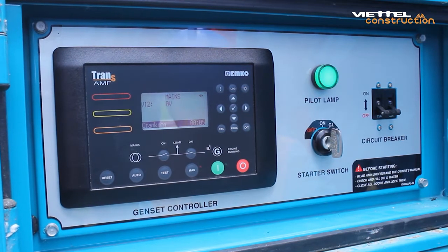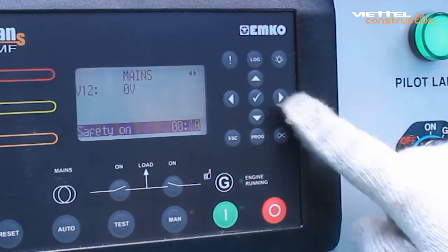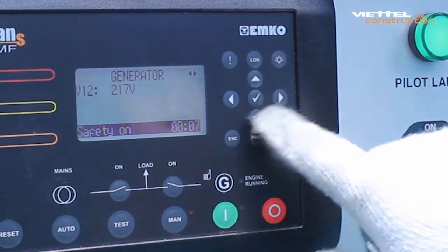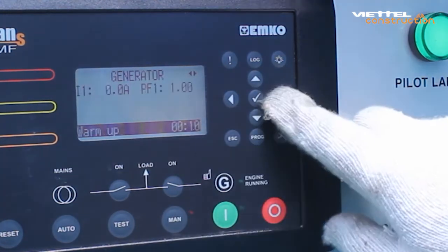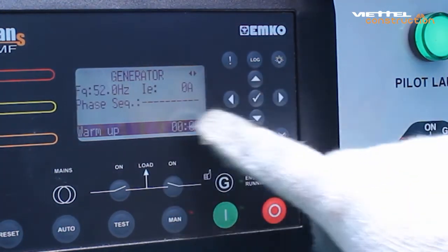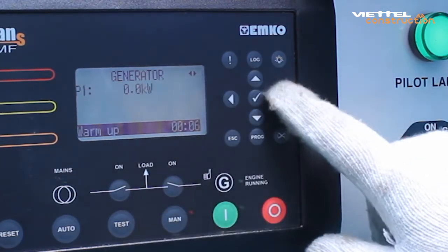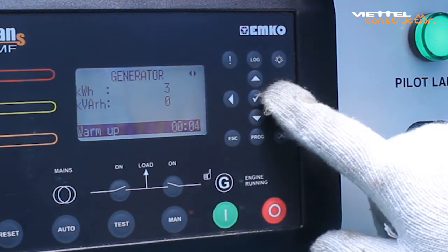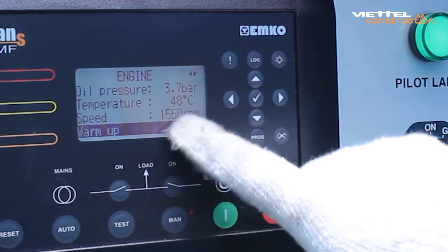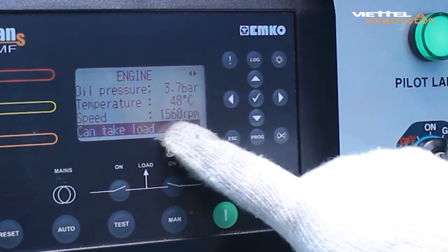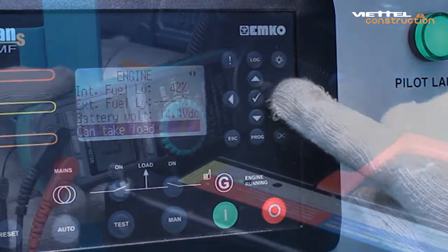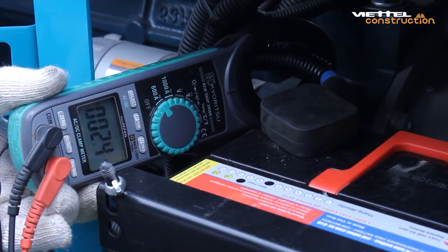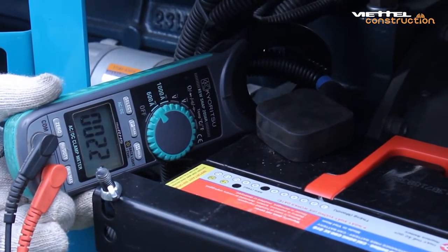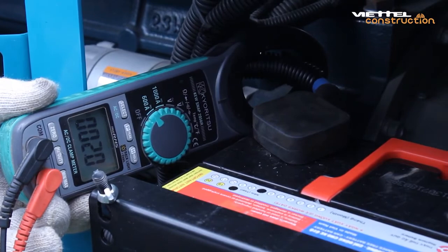According to the following parameters in the controller: voltage equal to 220/380 volts plus or minus 2.5%, frequency equal to 50 Hz plus or minus 5%. The engine speed is about 1500 to 1570 revolutions per minute. Check the battery charging system. Check the crocodile clips of the battery to make sure it has a charging current.